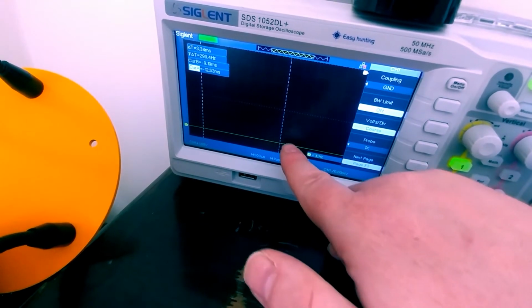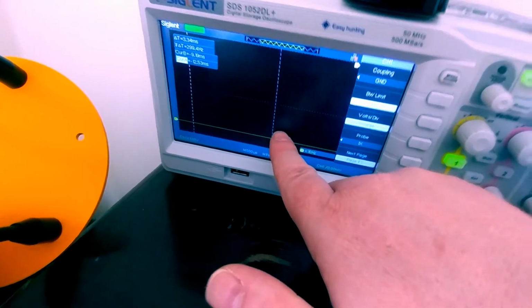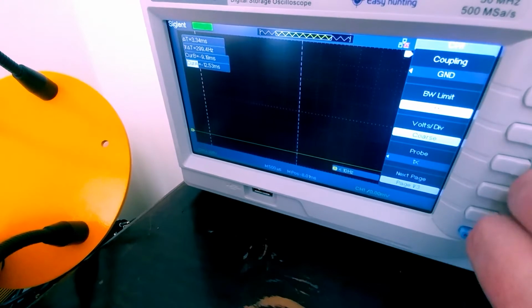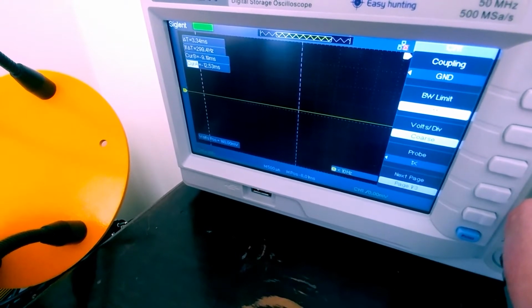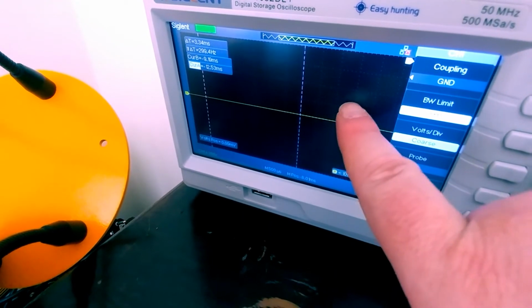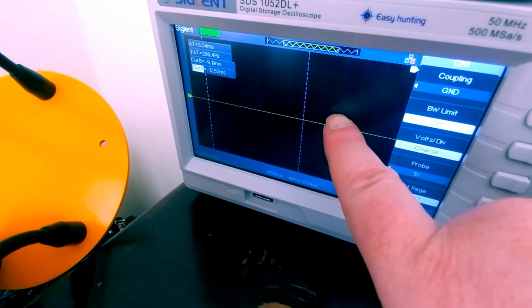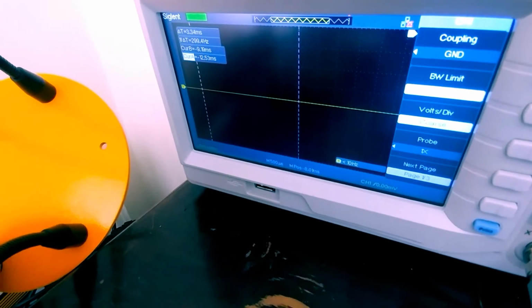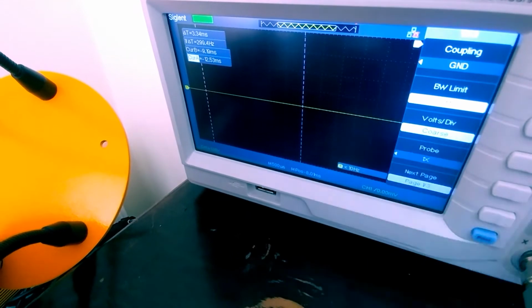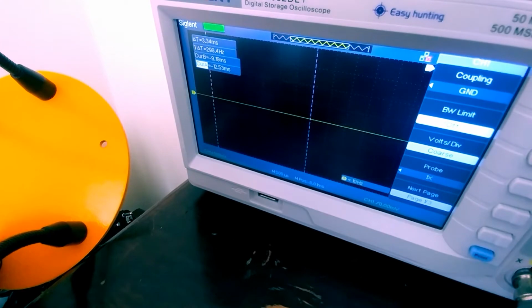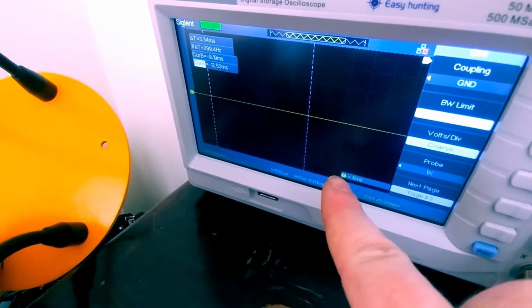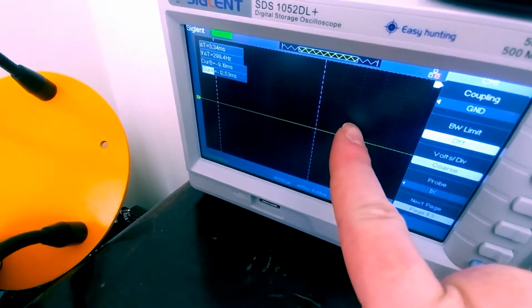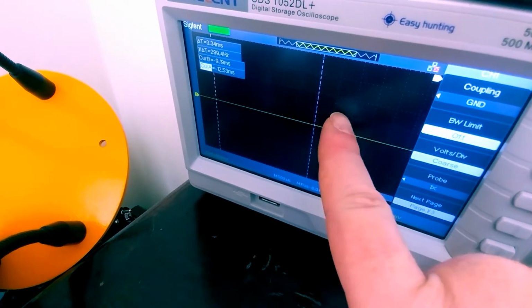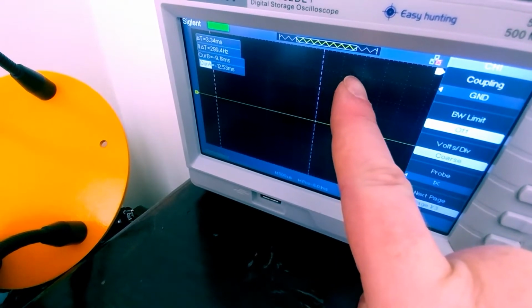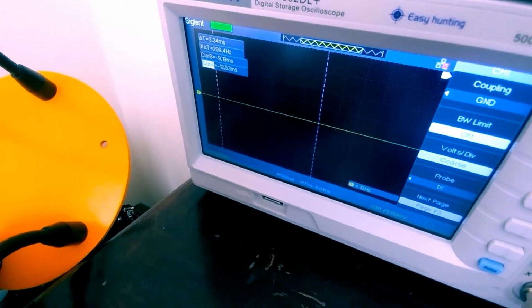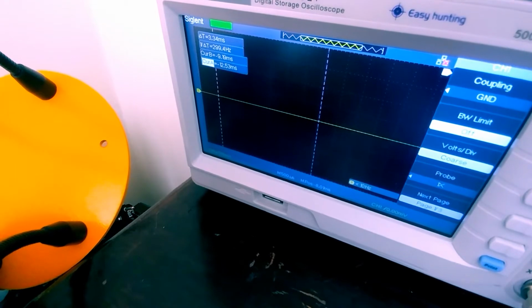If I had it set to 1 volt, then when I see a corresponding change up to this first square value, or let's say I'll set it up here, this is a little bit easier to view. If this increases by one value heading up this way, the next line, then that means that value equates to about 1 volt DC. Now if it goes up to 2, then that would be 2 volts. Again, I want to set my measurement to 500 millivolts. As I know the multimeter was giving me about 1.5 volts, then I should see that this increases by not just 1, but 2. So 500 millivolts plus 500 millivolts will give me a volt, and almost up to this third line here for 1.5, or around 1.43, I think is what we were seeing. It shouldn't quite touch that line, but it's going to be a much more accurate measurement.